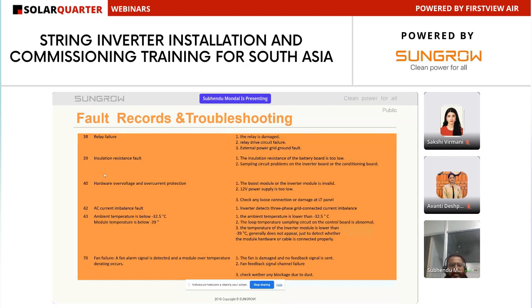40 is a hardware related issue. 40 is IGBT failure. The IGBT is a very sensitive and very important part of the inverter. So 40 is related to IGBT failure. When the inverter IGBT fails, it may be an internal problem or due to an external problem. At that time the 40 alarm will occur. 42 AC current imbalance. 43 ambient temperature is below -32.5 and -39 degrees. So this is also a hardware related issue. 70 is fan. A fan alarm signals detected over temperature or derating. Sometimes derating occurs due to the fan. In that case, we have to clean the fan, and if the issue is not resolved, we have to replace the fan. Check whether there is any blockage inside the fan terminal.